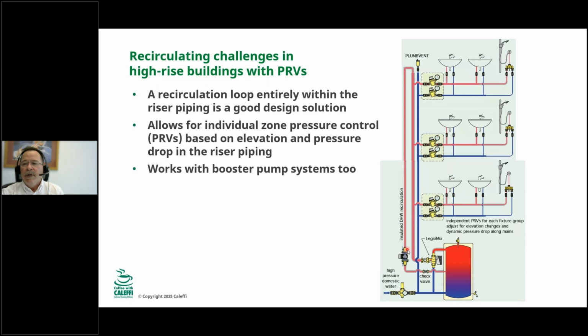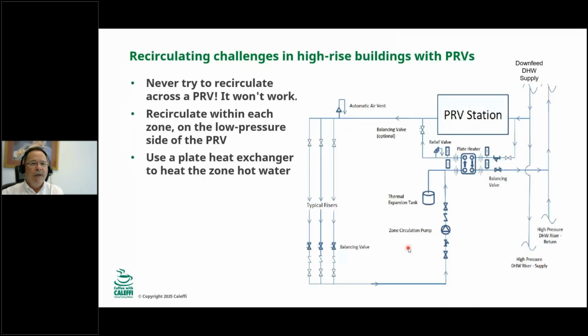Another way to do it, now this is a different diagram, but I don't have a better one. The rule is never try to recirculate across a PRV. It will not work. You can't do it. You can't recirculate and then push water back into a high pressure system on the backside of a PRV. Over here on the far right is our high pressure piping. What you can do is set up a PRV station, and that PRV station is going to serve all of your risers and your balancing valves and everything out here, all your fixtures.